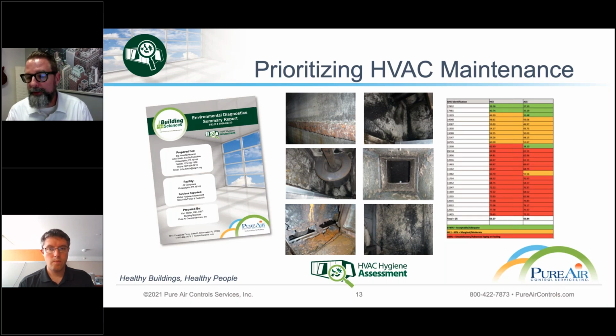Another thing Ross brought up was that many systems can't handle higher rated filters due to static pressure, and static pressure drops can be indicative of fouled coils, like you can see in this picture in the upper left, where airflow is impeded because the coils are so impacted by dust, debris, and this fiberglass breaking down. What makes matters worse is that the pressure affects the unit in such a way that these filters might start to bend or crumple, creating bypass and exacerbating the problem even more.